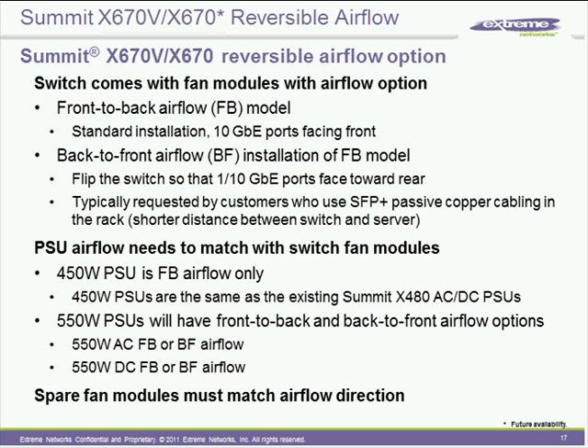And in case you choose front-to-back or back-to-front, you will have to have an associated power supply, because the power supply has its own airflow as well. And the spare fan modules must match the same direction, because it's not software controllable. So that's the hardware difference between front-to-back and back-to-front. That's what I wanted to mention about the reversible airflow.